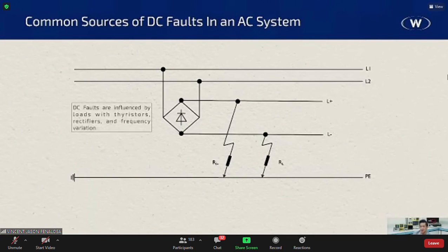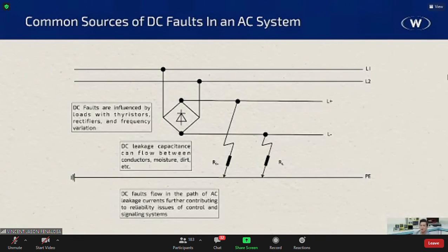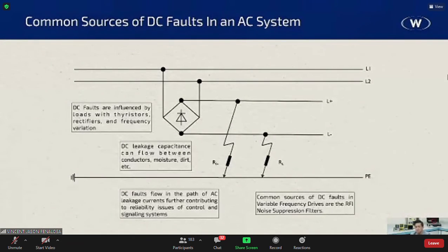And here are a couple of examples where you would find DC faults. DC faults are influenced by loads with thyristors, rectifiers, and frequency variation. Now, for the usual variable frequency drives that you probably have in your facilities, they're usually not coming from the power supply stage or the IGBT stage. They usually come from the noise filter. That's the one that gives out those DC leakage capacitance, right? Okay, so there you go, the noise suppression filters.